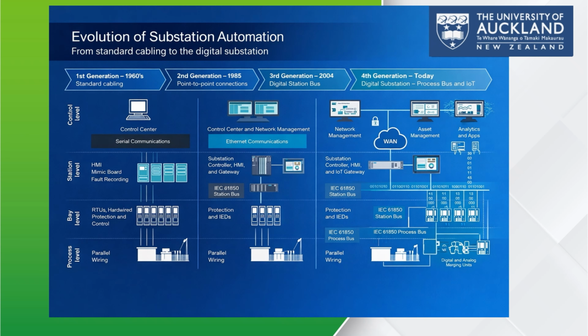In the second generation, around 1985, we moved to point-to-point communications. Stations gained better controllers and HMIs, and communications improved. However, each device still required its own physical connections, so scalability remained limited. So in the third generation, about 2004, IEC 61850 was introduced, the game changer, along with the station bus using Ethernet. So intelligent electronic devices, or IEDs in short, begin to talk to each other over a common network. This reduced wiring, improved interoperability across vendors, and dramatically sped up data exchange for protection and control. We still had parallel wiring to the process equipment, but the station-level digitization was a major leap.